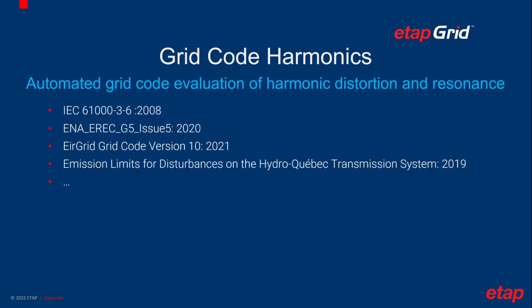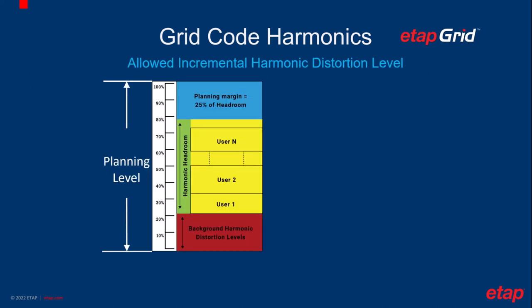This type of harmonic analysis, considering various power grid operation conditions, has been required by IEC 61000-3-6 and specified in many country grid codes such as ENA G55 in UK, EirGrid in Ireland, Hydro-Québec in Canada, and many others. Let's first have an understanding of what's the requirement by the grid code.